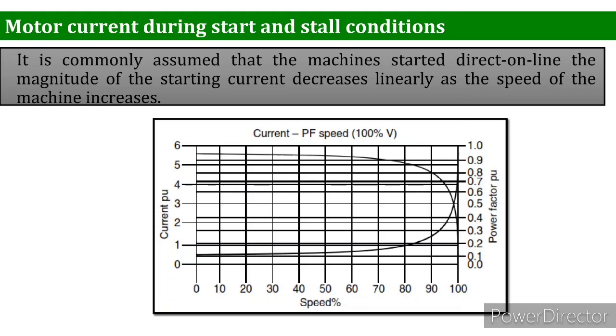The magnitude of the starting current decreases linearly as the speed of the machine increases. This is not true for the normal design. The starting current remains approximately constant at initial values for 80 to 90%. Like the graph we have, you can see that when determining the current and time constant of the overload protection, it can be assumed that the motor starting current remains constant and equal to the standstill value for the whole starting time. In the graph we have speed, and on the right hand side on the y-axis we have the power factor per unit, and on the left hand side we have the current per unit.